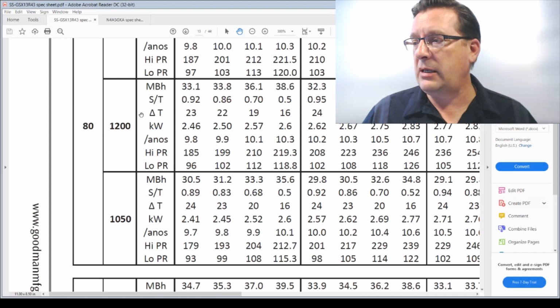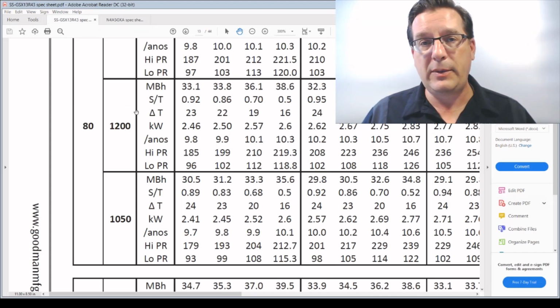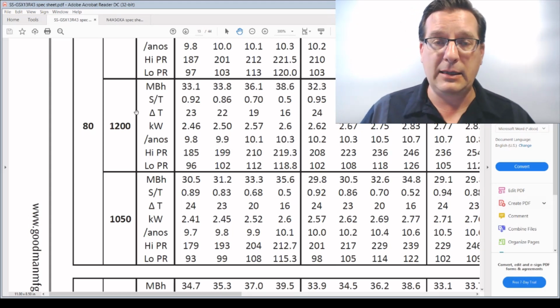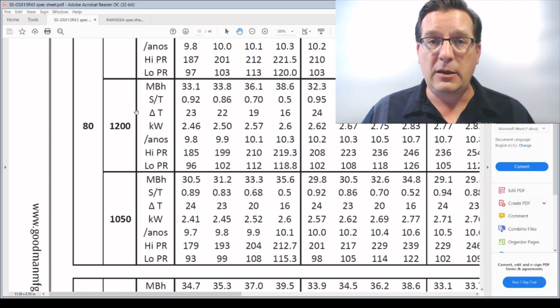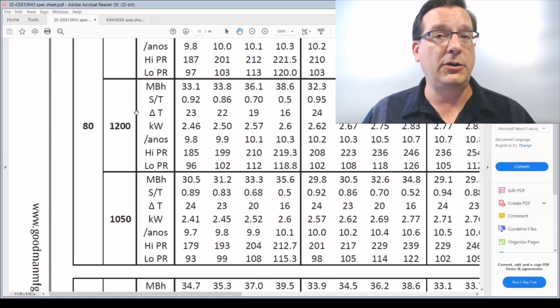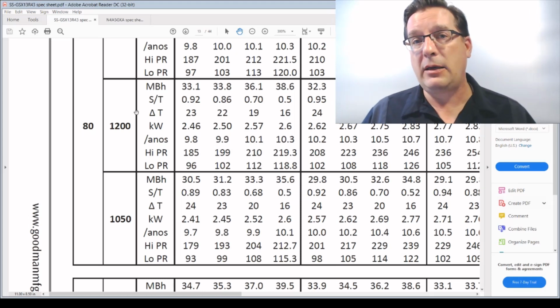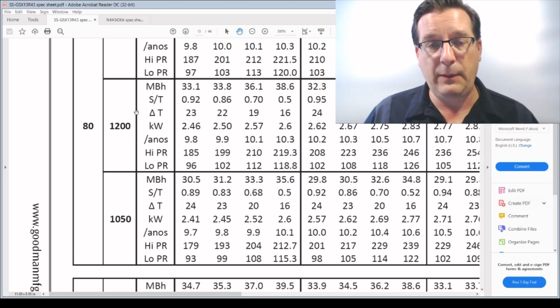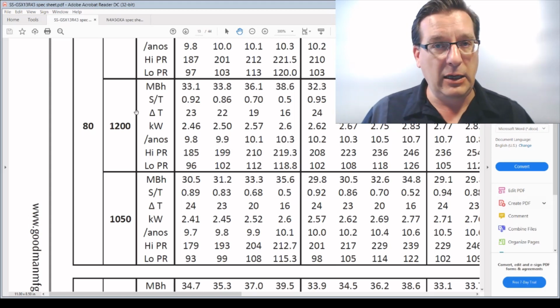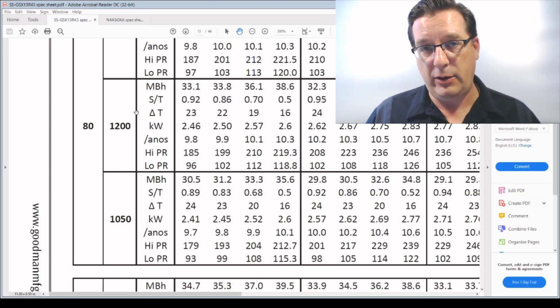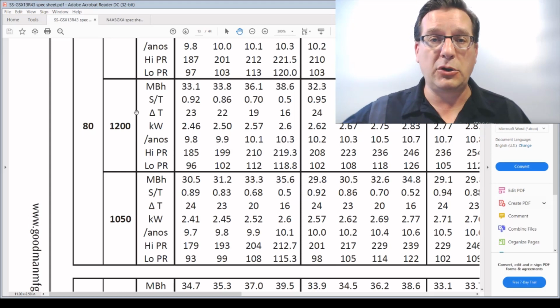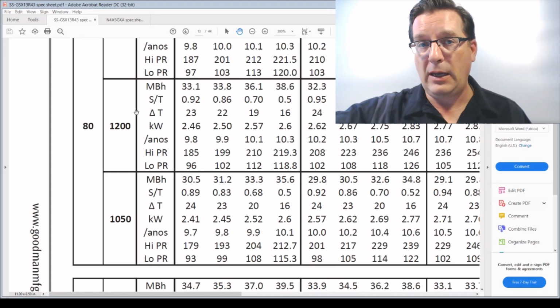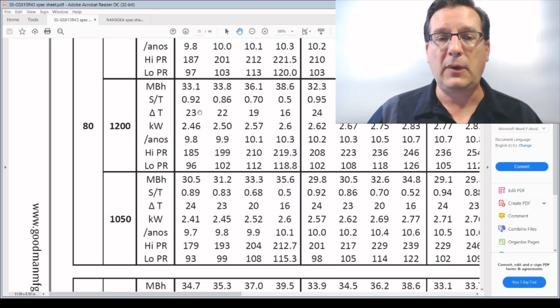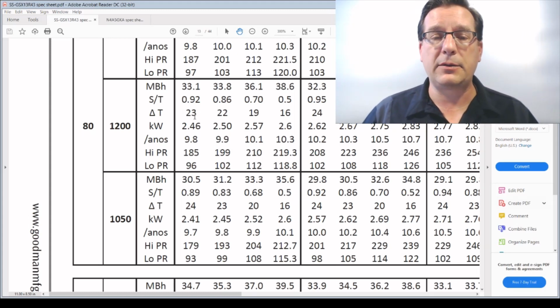The next column given is delta T. The triangle symbol means delta, which also means change in value of whatever comes next. Because the next symbol is a T, and T stands for temperature, this means change in value of temperature. This is also called your temperature difference, temperature drop, temperature split. All those mean the same thing. This means the difference between the return air entering the evaporator coil and the supply air leaving the evaporator coil. As we have said, there's going to be a temperature drop as the air flows across the evaporator coil, and that is called the delta T. So under these conditions, that delta T would be 23 degrees.